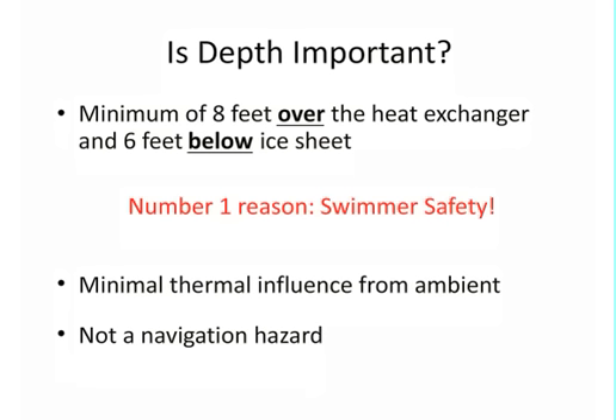Yes. A minimum of 8 feet over the top of the heat exchanger, depending on the type you install. In the northern parts of the country, we want a minimum of 6 feet below the ice sheet. The other point I really harp on with pond loops is that the number one reason for depth is swimmer safety.